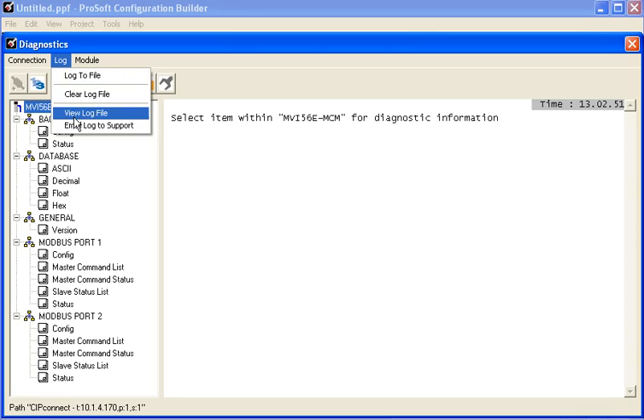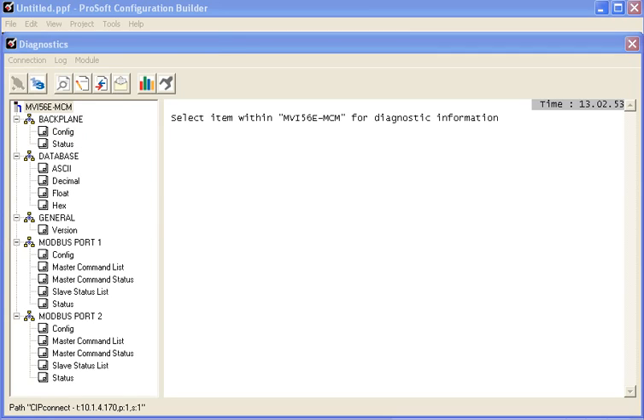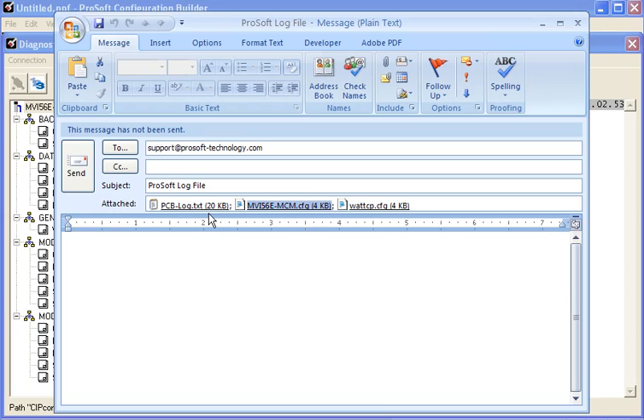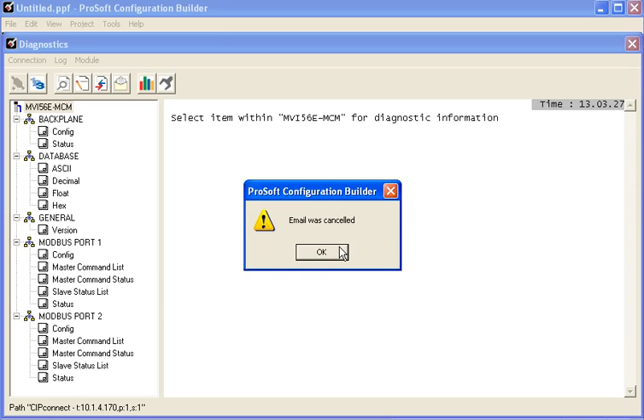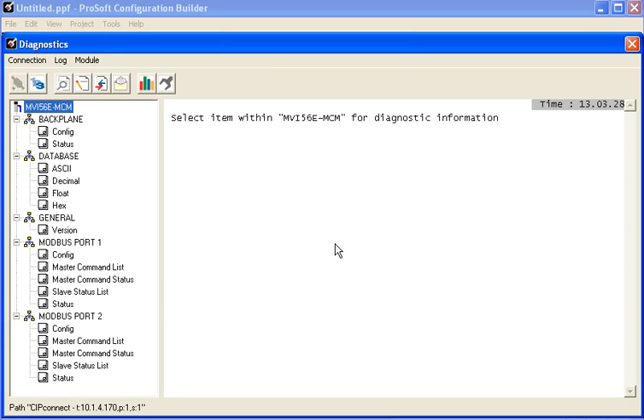Now I'll show you one example of how this log file might actually be used. So up top we can click on Log and Email Log to Support. And if you have a mail client such as Outlook, it'll open a new email window and you see that we have three files attached. We have the wattcp.cfg file, which is your Ethernet settings. We have the MVI56E-Config file, which is the complete configuration of the module, and we have the PCB log file. These are three key pieces of information that may be needed by our technical support staff when opening a new support case with our technical support department.